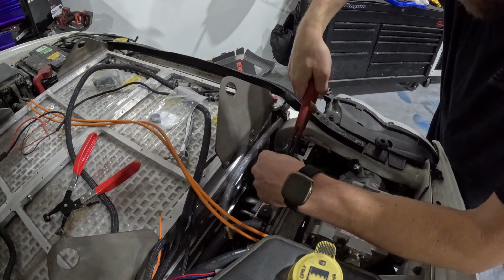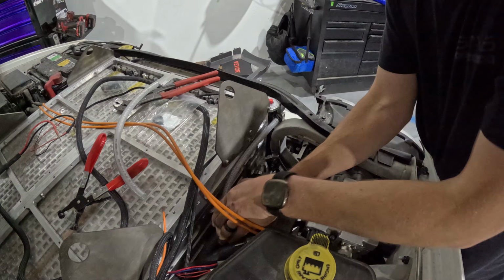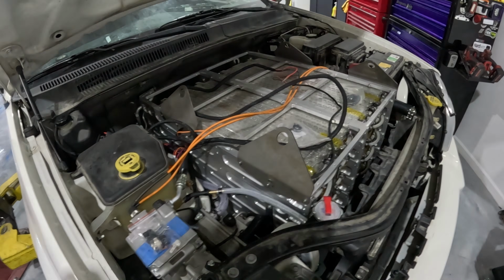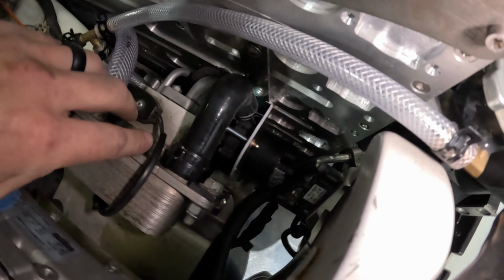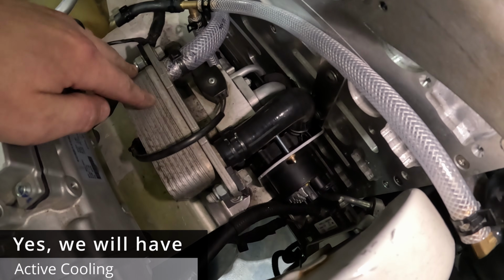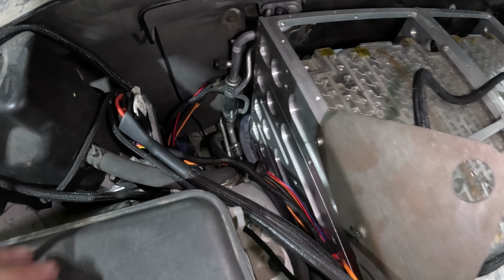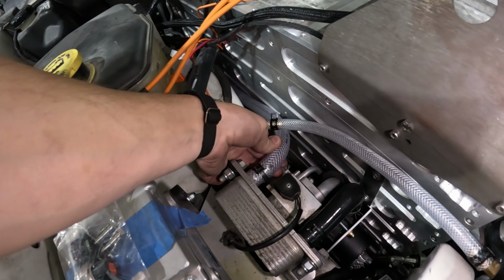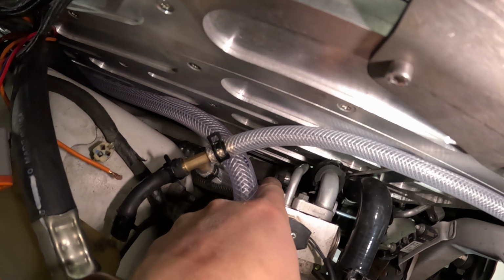So now it'll be time to mount the battery pump. We do have everything in now. There's the pump down there. It goes directly into the chiller block, out of the chiller block, down to the Ys that I installed the other day, then to each battery and back, and then up to here, the inlet of the pump.